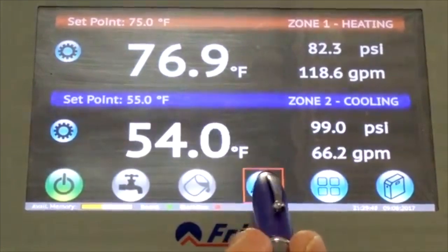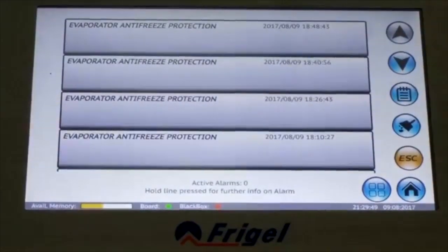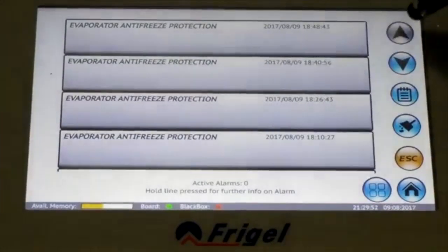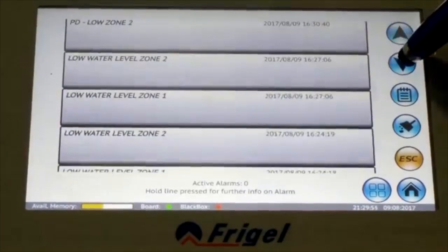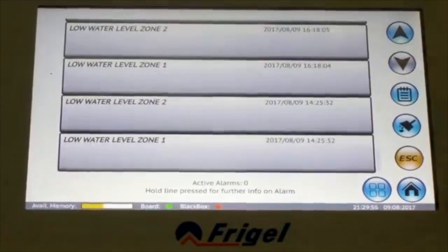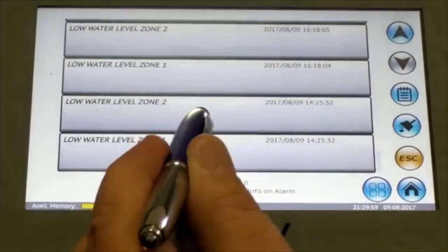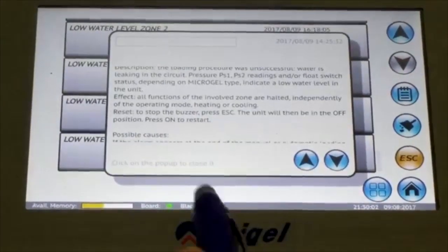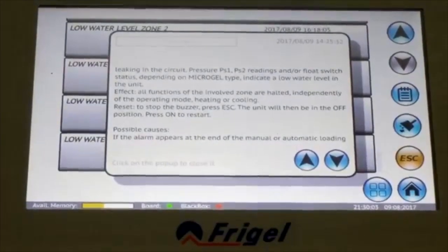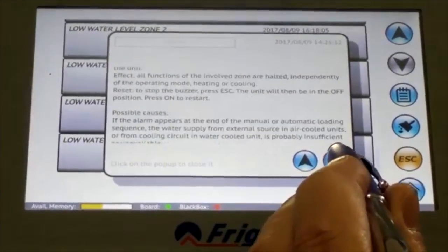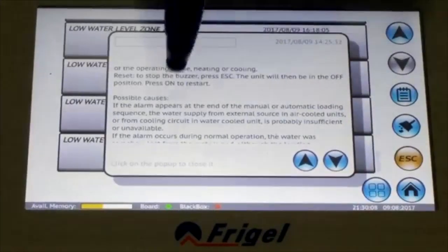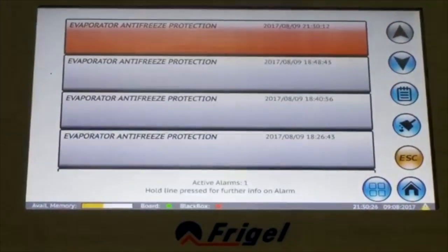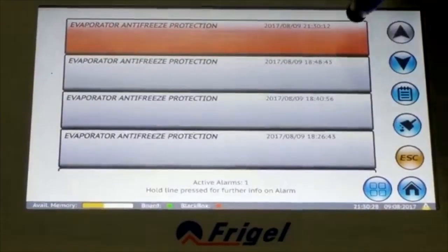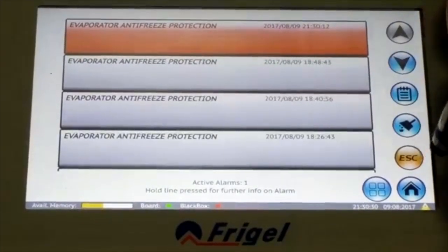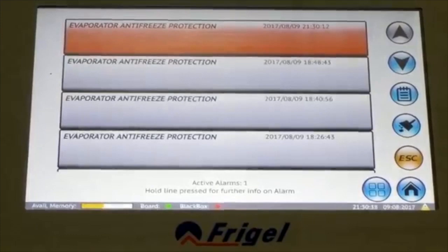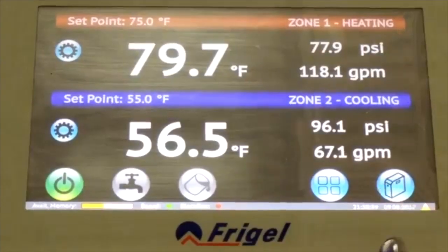Touching the alarm icon on the home page, you can see a dated alarm log. By pressing and holding an alarm notice, a complete explanation will be displayed in addition to troubleshooting recommendations, all in full language with no codes. Here we have an active alarm which can be silenced by the escape button. The alarm remains active until corrected.